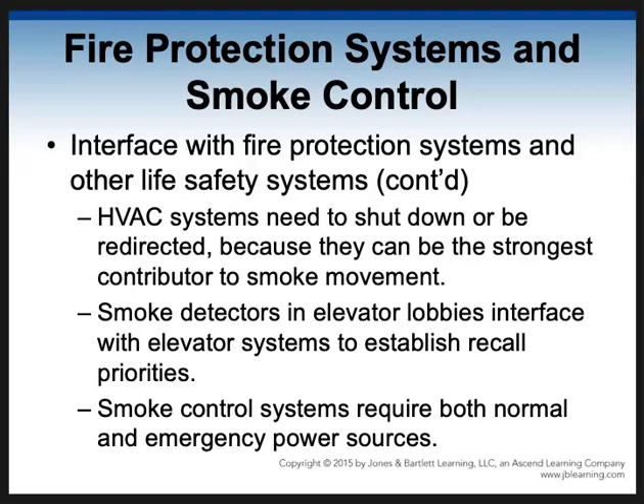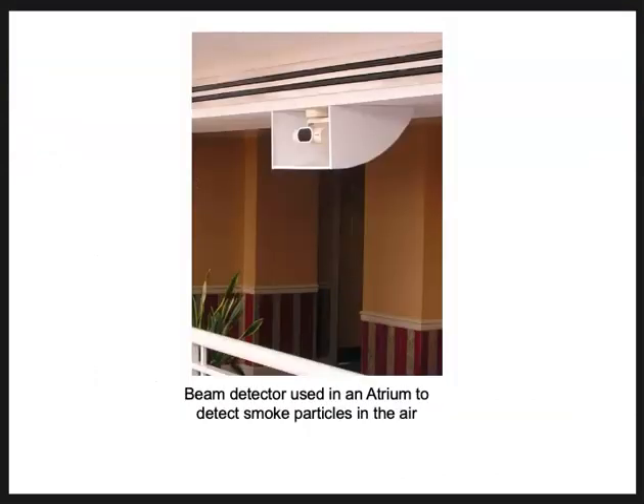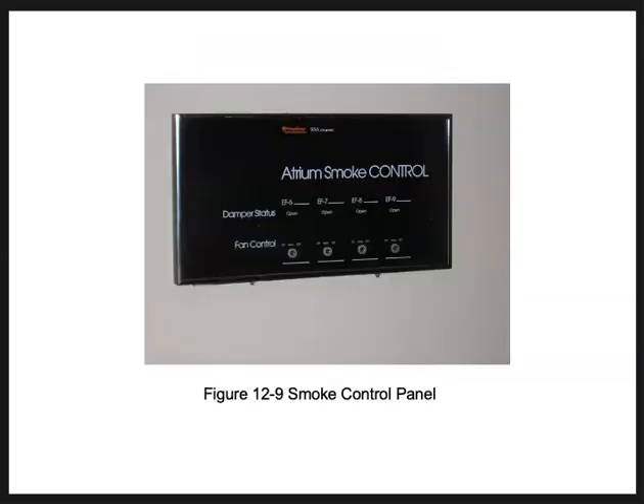Smoke detectors are usually in the elevator lobbies, and they're going to be throughout the building that initiate a lot of this control, doors closing, vents opening, some vents closing. They require battery or usually generator power backup. So here's very common in atriums. We're going to use beam detectors to detect smoke particles in the air, and then that's going to set off the alarms, turn on the smoke control, and then if the heat builds up enough, the sprinklers will turn on, and they're all going to work together.